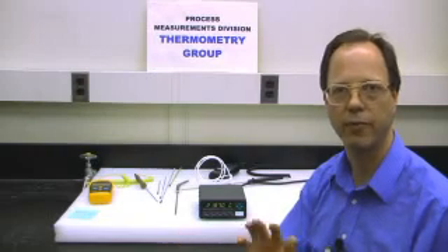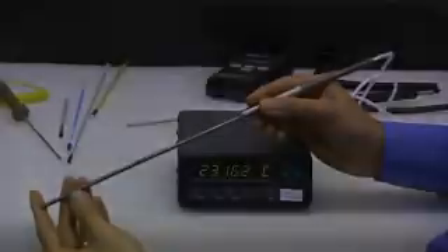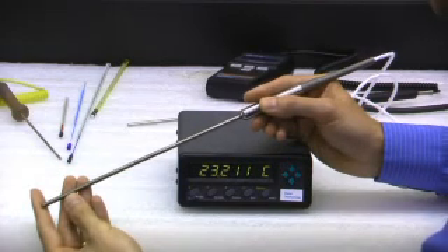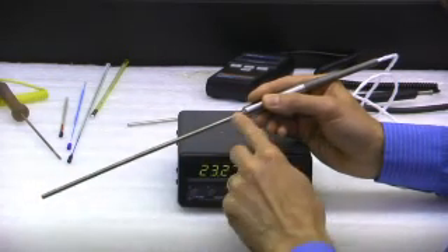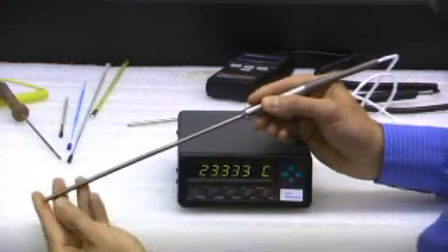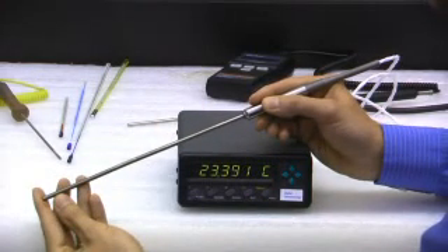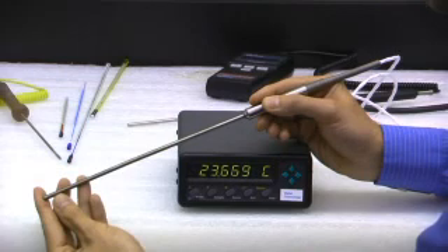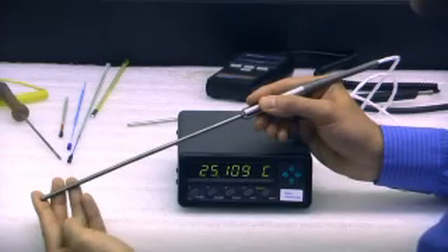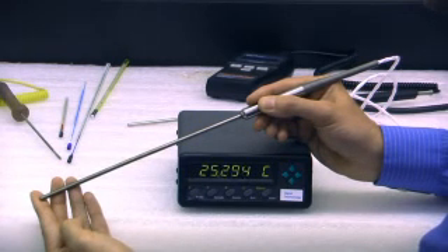Now I'll talk about the different types of alternatives we can use. There are several sensor types. Many of the sensor types are all packaged in the same metal sheath probe. But it's important to know what type of sensor your thermometer is based on. One common type is the platinum resistance thermometer. That's called PRT for short. It's often called resistance temperature detector, RTD as well. A platinum resistance thermometer with a digital readout is very close to being a universal replacement for many mercury thermometers. It has good accuracy and a good temperature range of use.